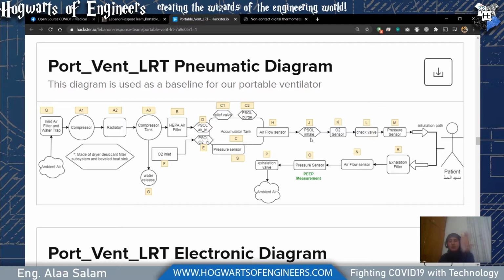When you have a ventilator working and a patient working, you need them to be synchronized. You can't have a patient inhaling during the exhalation cycle, and you cannot have them release that air in the inhalation cycle. So we need to control them. We control these cycles with the P-sol inhale and P-sol exhale valves.